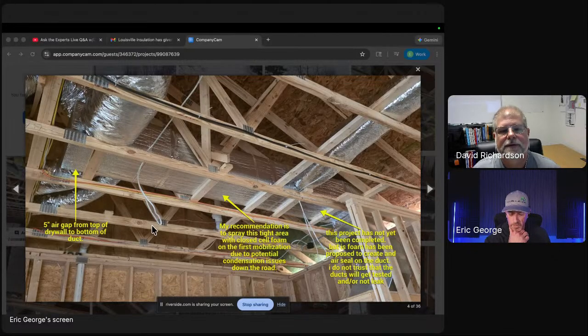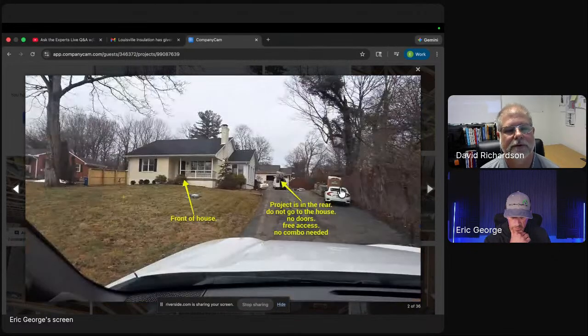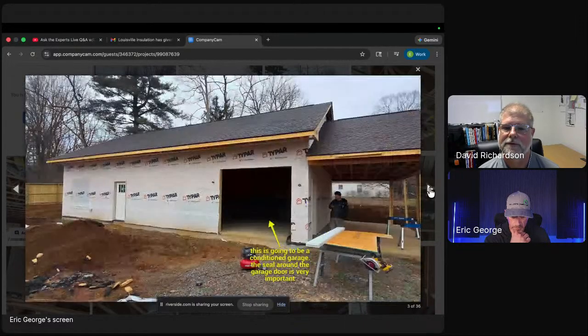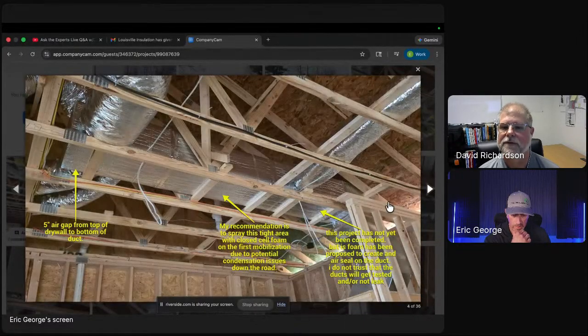Okay, so it looks like this is a garage in the back. It's going to be conditioned space. And he's got a duct system going through the attic directly above the ceiling joist, so he's got a 5-inch air gap from the top of the drywall to the bottom of the duct. The recommendation is to spray this tight area with closed cell foam on the first trip out, due to potential condensation issues down the road. I would say that's a good idea, especially because they're using bubble wrap insulation. Absolutely.